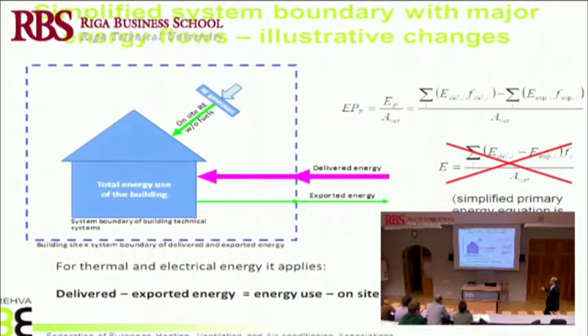This on-site production can be directly subtracted from the delivered energy if it is fully utilized in the building. But if you have, for example, a lot of solar production in summer and no corresponding load in the building, you need to export this energy to the grid. So the basic energy balance is shown here for both thermal and electrical energy: delivered minus exported energy equals energy use in the building minus on-site renewable energy. This balance is shown by the system boundary line.